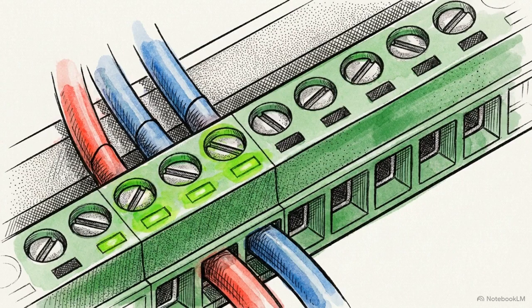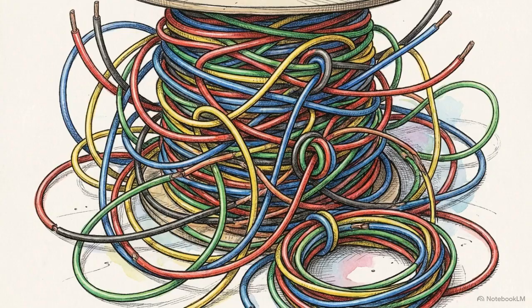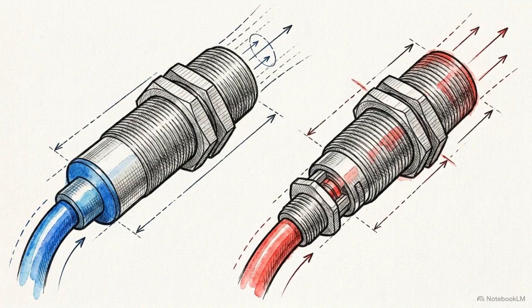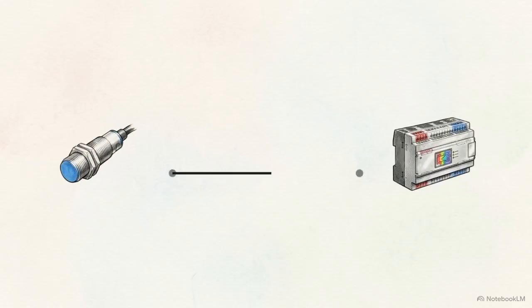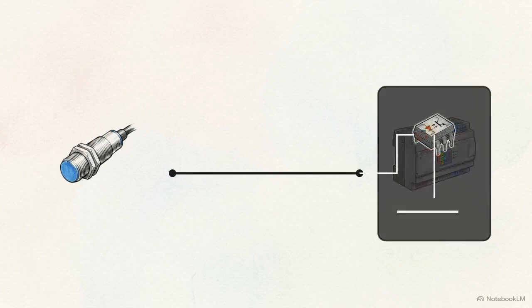terminals of the PLC. This introduces the most frequently misunderstood concept in panel wiring, the difference between PNP and NPN architectures, often referred to as source and sink. Look at this cross-sectional diagram of a proximity sensor wired directly to a PLC input. To understand the circuit, you have to track the physical direction of the electron current, not just the voltage potential.